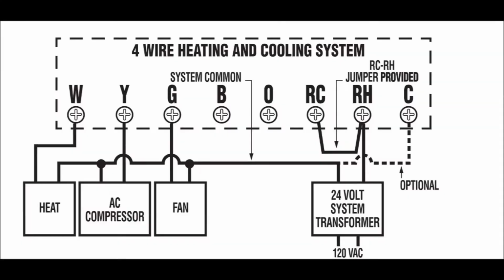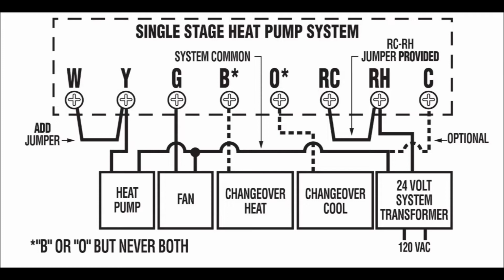Okay, here you can see the old system where you had the heat and the compressor separately. It wasn't a heat pump, so the white turns the heat on, and the yellow turns the compressor on, and then the green turns the fan on. So basically, whenever you wanted heat, the white would get activated. Now here with the heat pump, you have the yellow, which is the compressor signal.